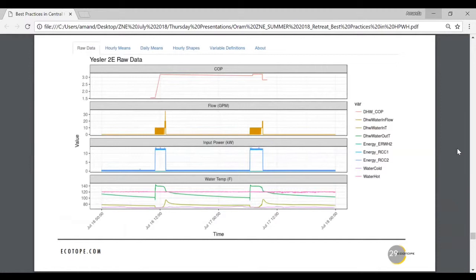Distribution system or for the main heating? It's for just the heat pumps, so it's just the primary plant. Right now we just turn 2 heat pumps on, run it for about 4 hours. We heat up 2,500 gallons of storage, wait for the next call. We let our storage drift down to about 90 in the middle, fire it, and then heat it back up. We can do that, we can control when we fire based on what that set point is. We can also have a little control over additional firings.